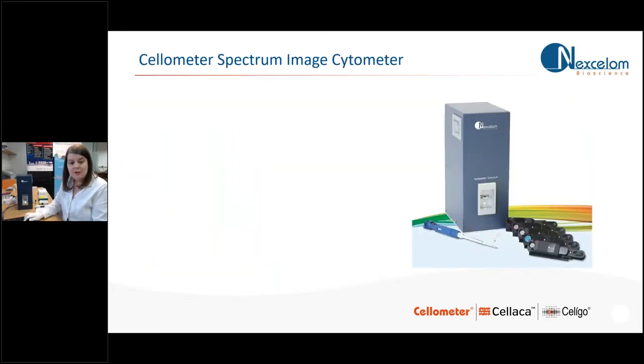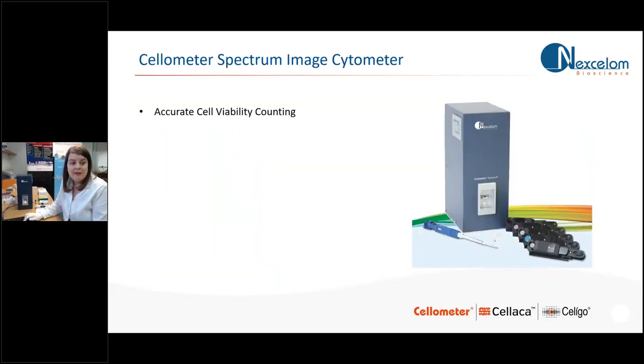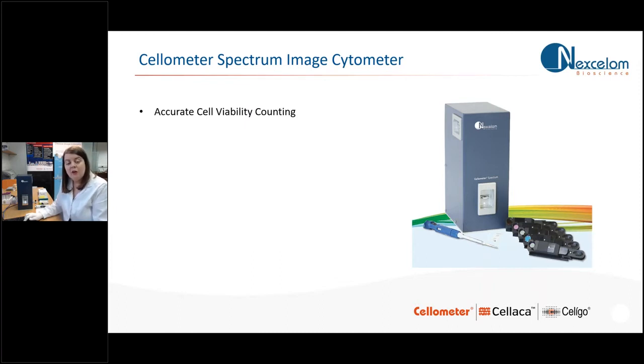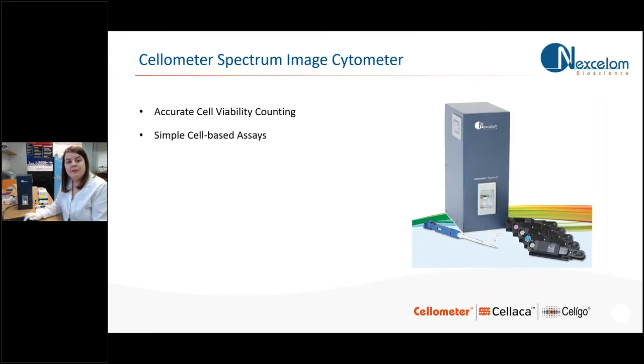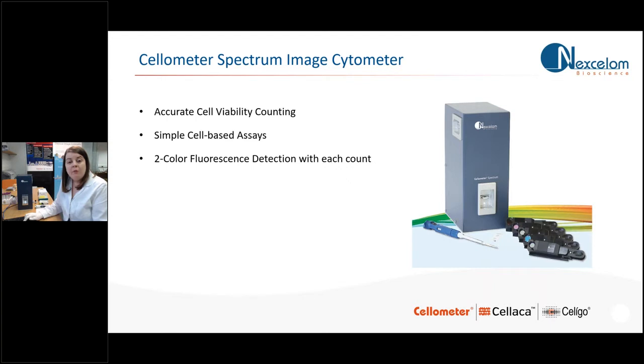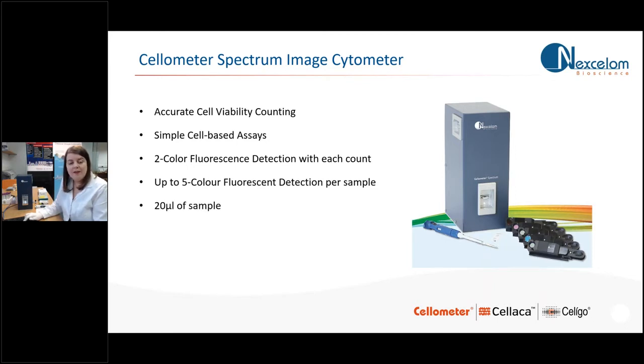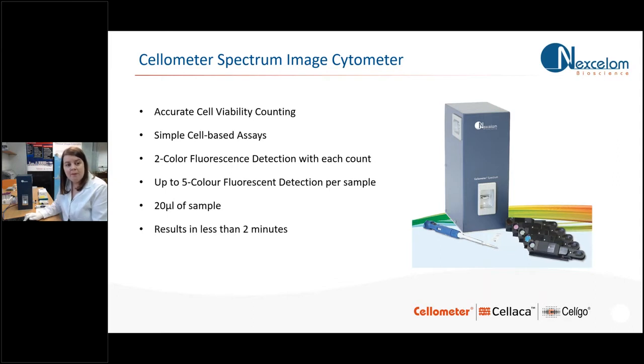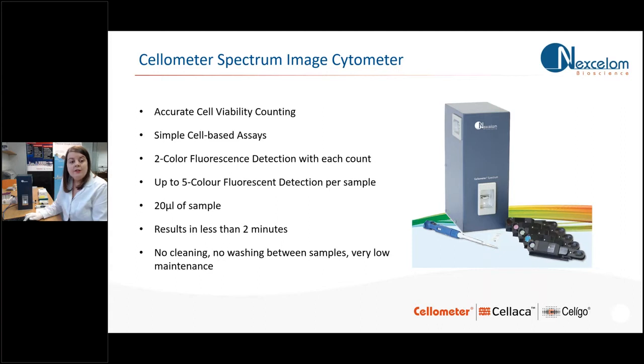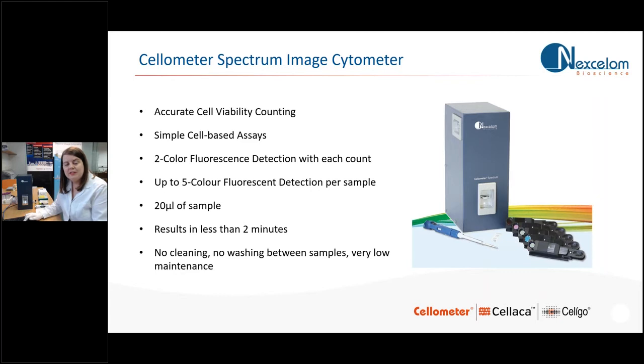So to summarize what you can expect from your Spectrum, you can expect accurate cell viability testing and counting and concentration measurements. You can also expect it to do simple cell-based assays. It will image in two colors of fluorescence per count, but you can image with up to five colors if you do them as separate counts. You only need 20 microliters of sample and you should get your results in less than two minutes. There's no fluidics within the system, so therefore there's no cleaning and there's no washing between samples. It's extremely low maintenance.